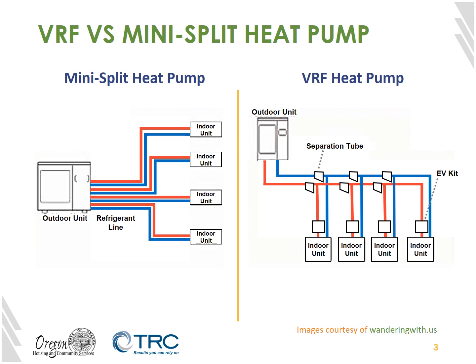On the right side of our screen, we have the VRF heat pump. And you'll notice just looking at it, one of the key differences is you're going to have a single supply line and a single suction line in this two-pipe system, or a single hot gas line and a single low pressure gas line. What's unique about this is, while a bit of an oversimplification, it's designed a bit like a plumbing supply system, where you have a main trunk and branches that go to each indoor head or indoor unit. This allows for a lot less refrigerant piping to be run through a building. And because of the way the system is designed and the volume of refrigerant the outdoor unit is capable of moving, you can have a great many more heads or indoor units connected to a single outdoor unit.